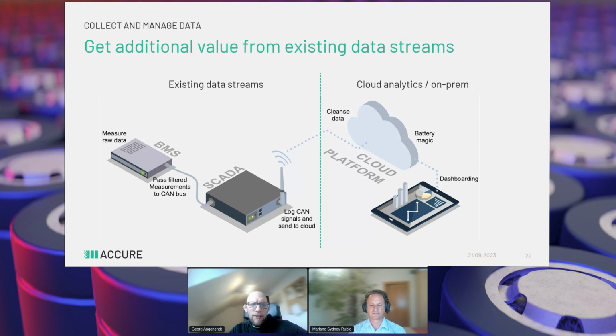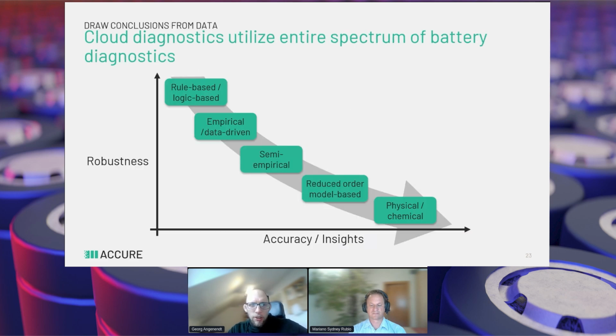But why is it necessary? Why can't the BMS do all this on its own? When it comes to battery diagnostics, you always have a trade-off between robustness and accuracy of these algorithms. When you design a BMS, you want algorithms which are highly robust, because of course you have to shut down if you see an overvoltage - there cannot be estimation errors. This is why in a BMS, often rule-based or logic-based algorithms are used, or partly empirical or data-driven algorithms.